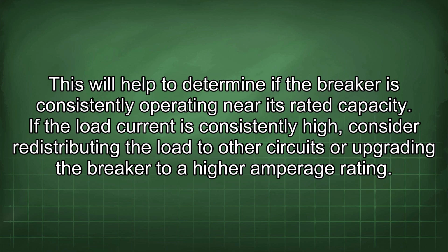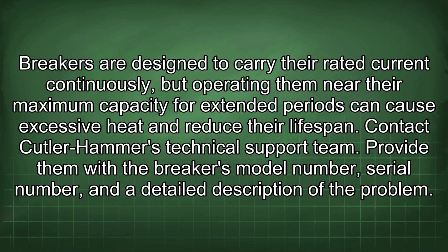If the load current is consistently high, consider redistributing the load to other circuits or upgrading the breaker to a higher amperage rating. Breakers are designed to carry their rated current continuously, but operating them near their maximum capacity for extended periods can cause excessive heat and reduce their lifespan.